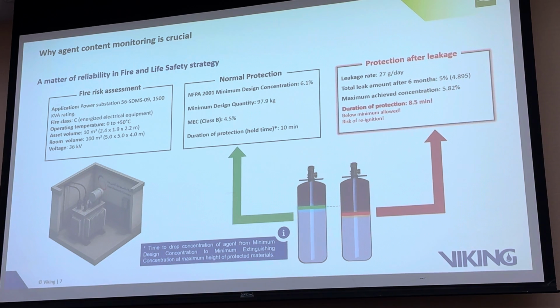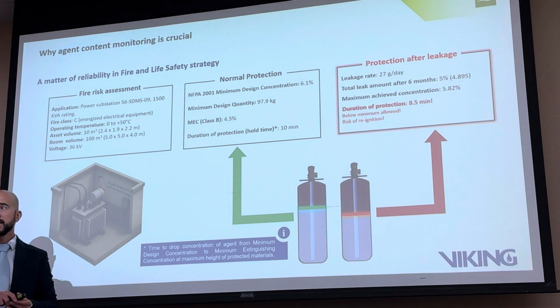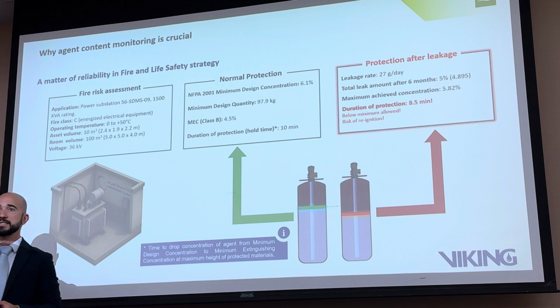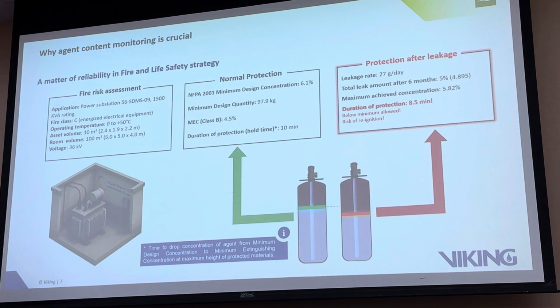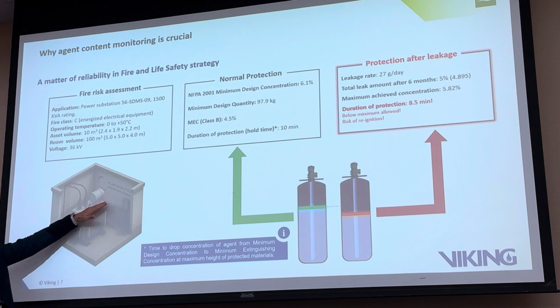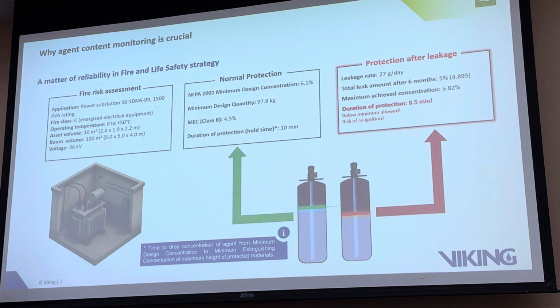So normal protection conditions, our system is working normally. So NFPA 2001 requires a minimum design concentration of 6.1 because it's a high hazard energized asset. So the minimum design quantity I calculated would be 97.9. The minimum extinguishing concentration is 4.5. That means I discharge and I reach 6.1. After 10 minutes, right? The concentration should not be below 4.5 at the heights of the asset, approximately 2.2 meters. That is the hold time, right? So this is how we design the systems.